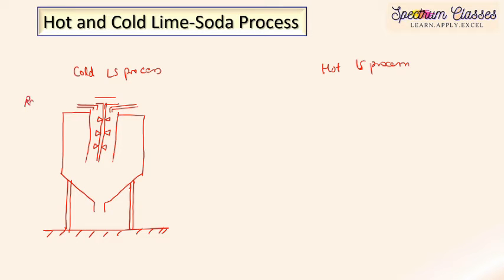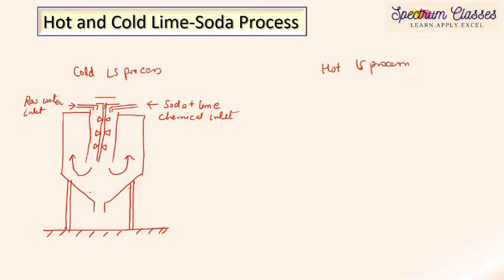In the cold lime soda process, raw water enters through the inlet and is mixed with soda-lime chemicals using a mechanical stirrer in the reaction chamber. The treated water flows upward, and sludge — consisting of suspended calcium carbonate and magnesium hydroxide particles — forms. These insoluble particles settle out and are referred to as sludge.